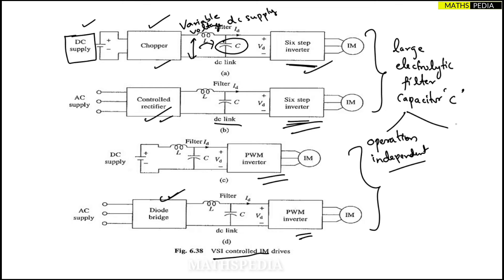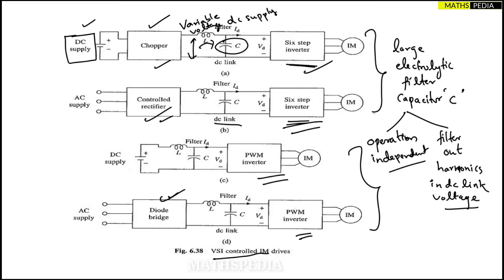The second purpose of the large electrolytic filter capacitor C is to filter out harmonics and fluctuations present in the DC link voltage. So to summarize: first purpose is to make the PWM or six-step inverter operate independently of the chopper, controlled rectifier, or diode bridge; second purpose is to filter out harmonics and voltage fluctuations.